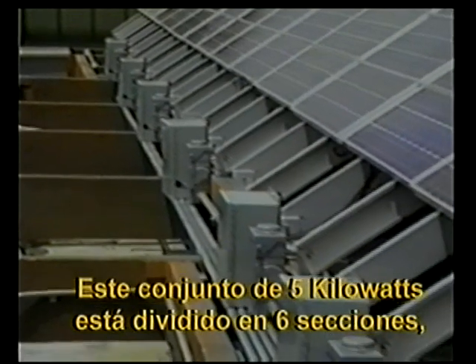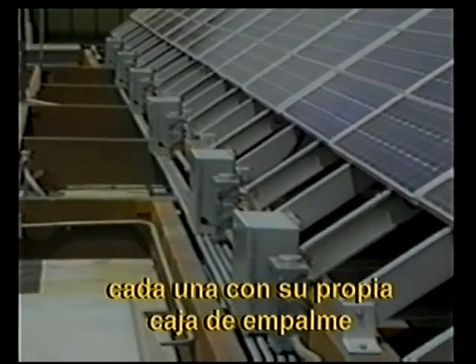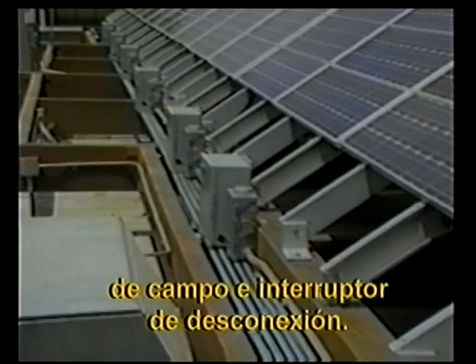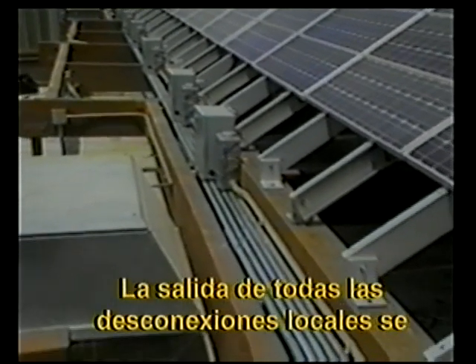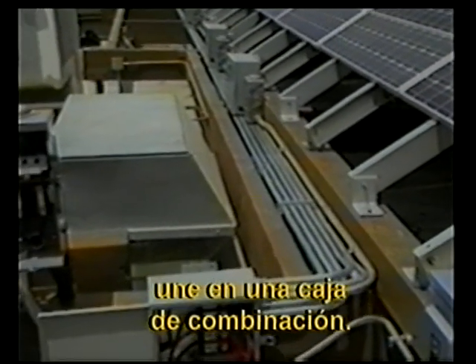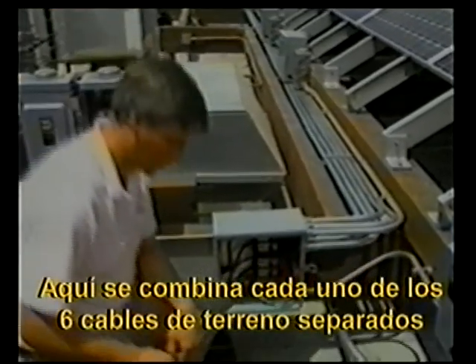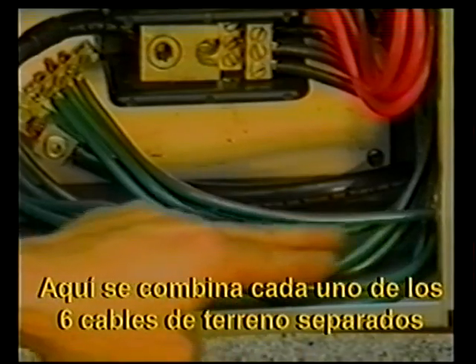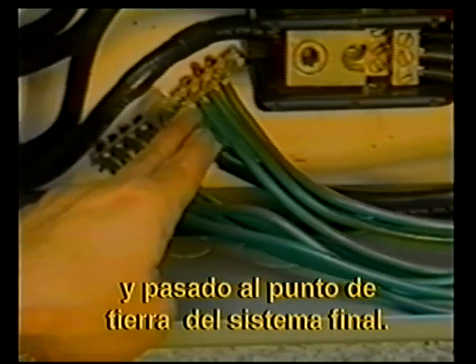This 5-kilowatt array is divided into 6 sections, each with its own field junction box and disconnect switch. The output from all the local disconnects come together in a combiner box. Here, each of the 6 separate ground wires is combined and passed on to the final system ground point.